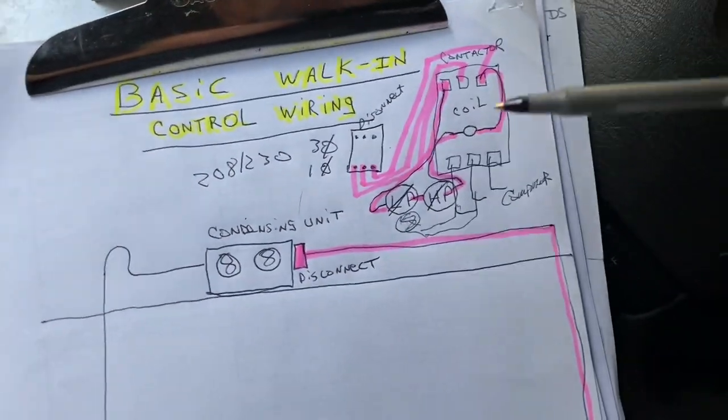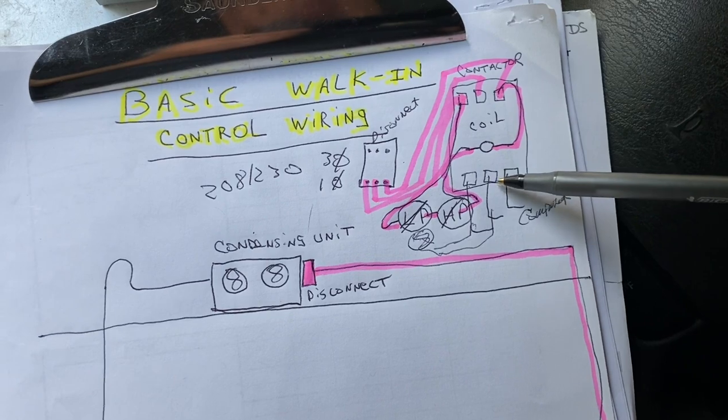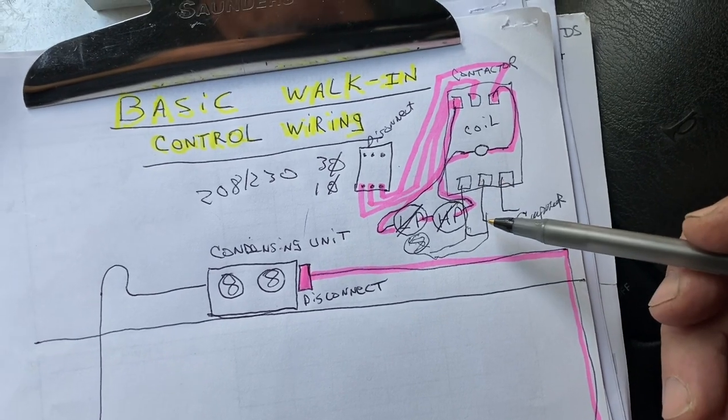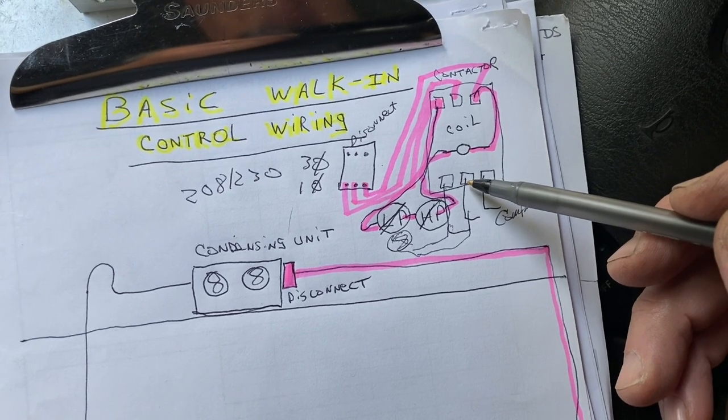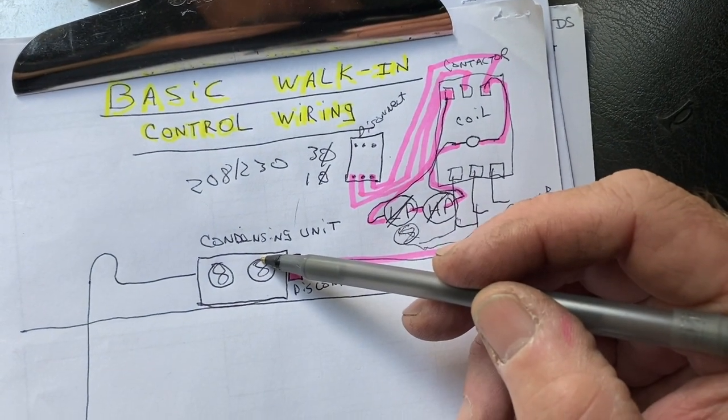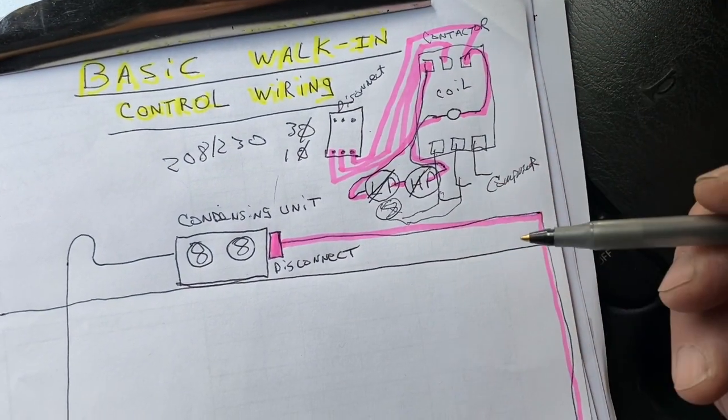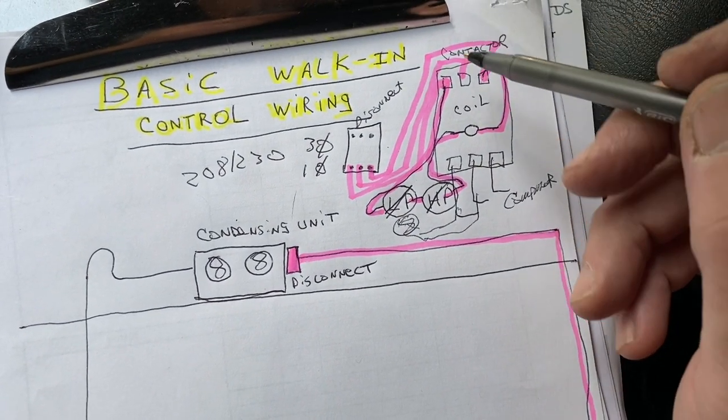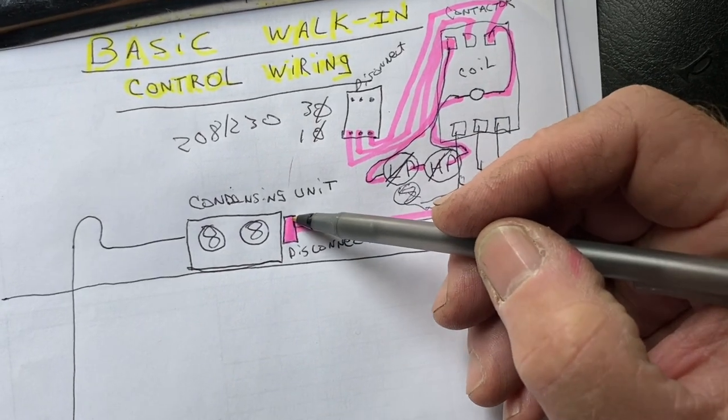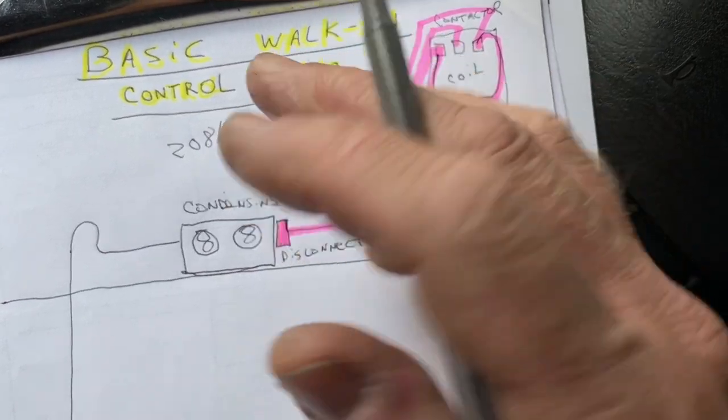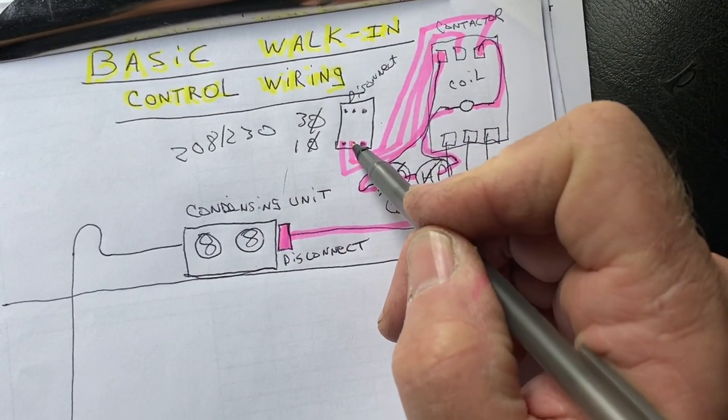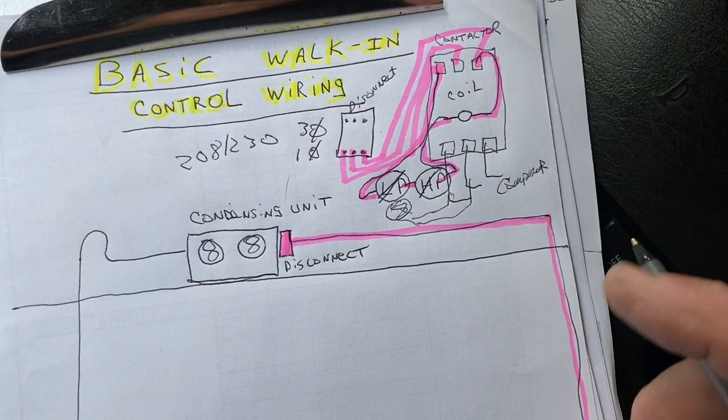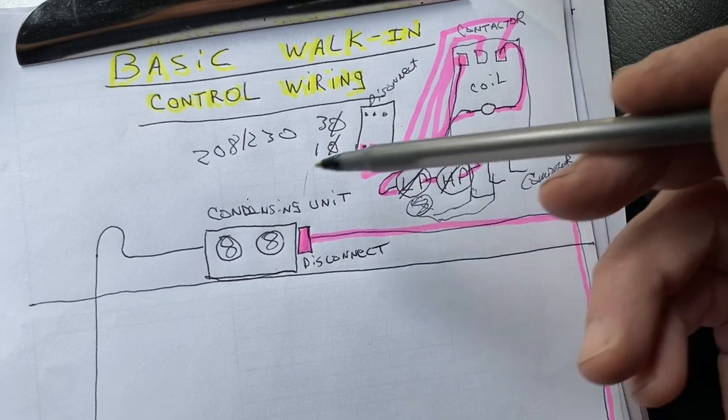One last thing to go over. If you have three phase and you have a scroll compressor in here, the scroll compressor is phase sensitive. It has to spin the right direction to pump. You'll have your gauges on it. You can listen to it. If your pressures are staying the same and it's running and your suction pressure is not dropping on your gauge, to correct that problem, shut off your disconnect and change any two wires. Just flip flop. You can take this one, put it here, take this one, put it here. And then that will get your rotation reversed for your compressor to run the right direction. If you have a scroll, on a recip, it doesn't matter which way it goes.